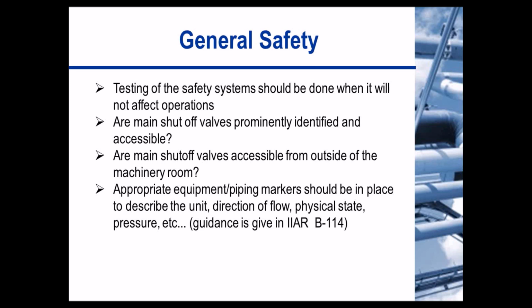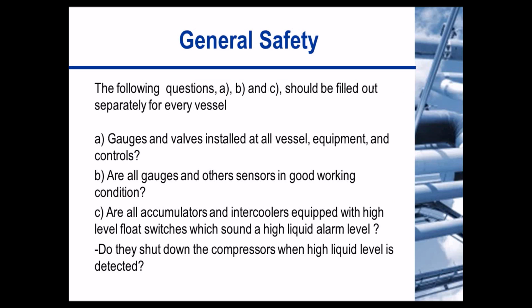Having the appropriate equipment and piping markers should be in place to describe the unit, direction of flow, physical state, pressure, etc. If you need to know more about what that entails, guidance is given in IIAR Bulletin 114. The general safety inspection checklist also contains three questions that should be answered for every vessel. The following questions, A, B, and C, should be filled out, and this includes gauges and valves installed at every equipment, vessel, and control. Are gauges and other sensors in good working condition? Also, are all accumulators and intercoolers equipped with high-level float switches with a high liquid level alarm? Also, do they shut down the compressor when high liquid level is detected?